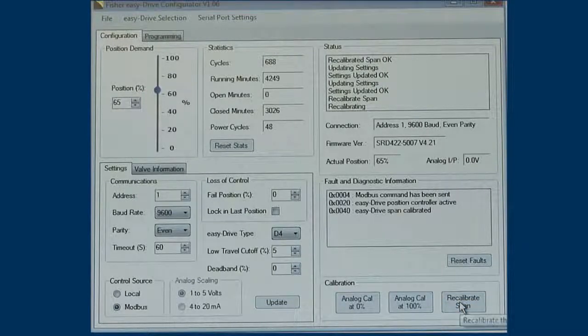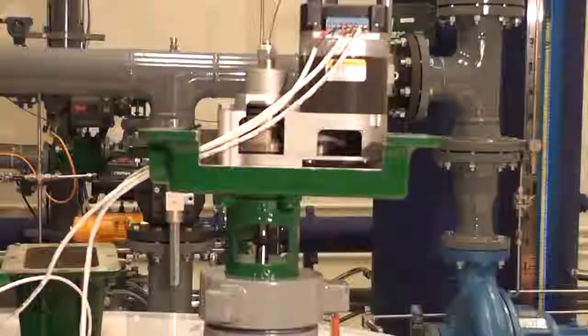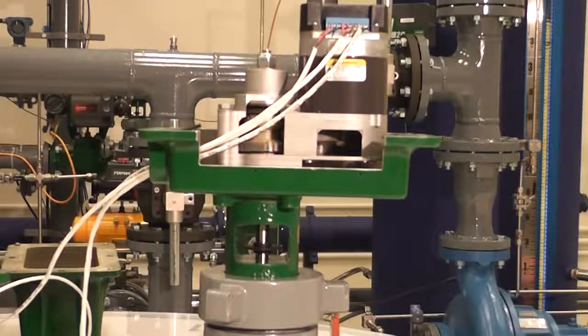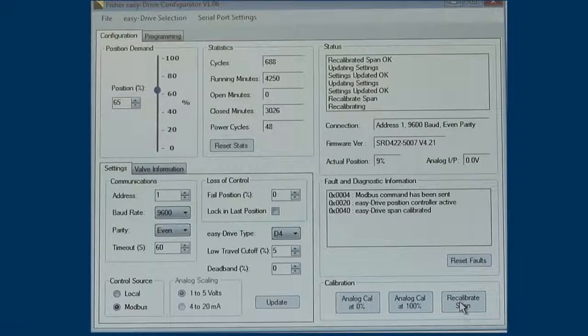Now click Recalibrate Span in the lower right-hand corner of the software. For the D4 valve, this should drive the valve plug into the seat and then return the travel to the Modbus span setting. In this case, we are at 65%.